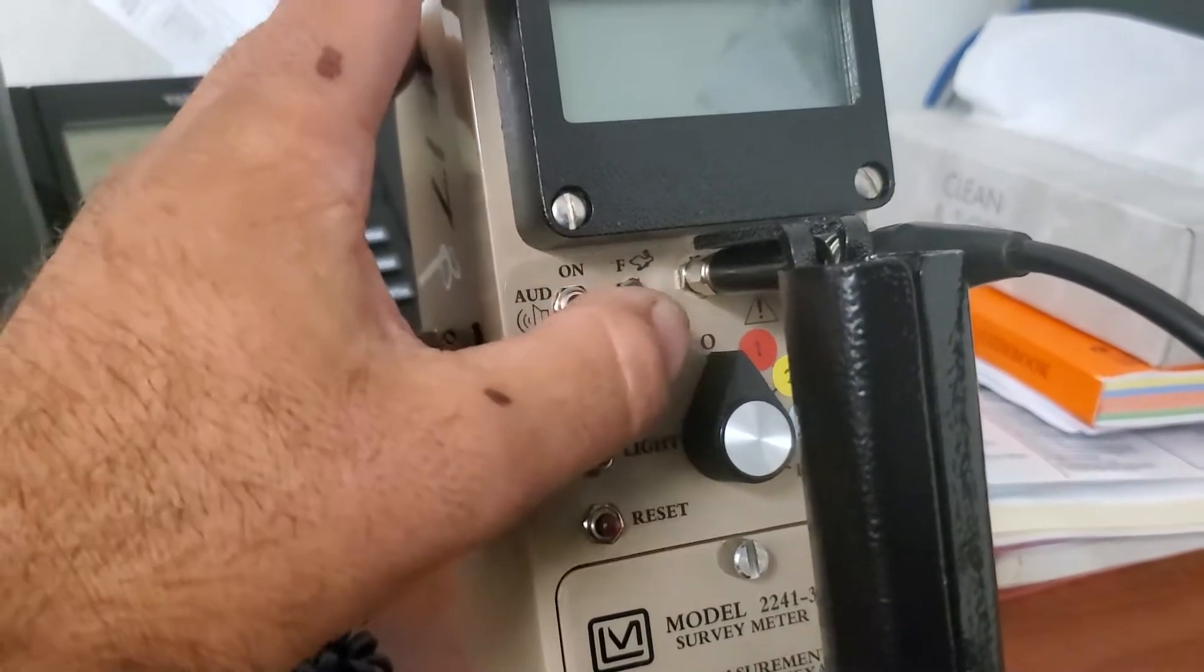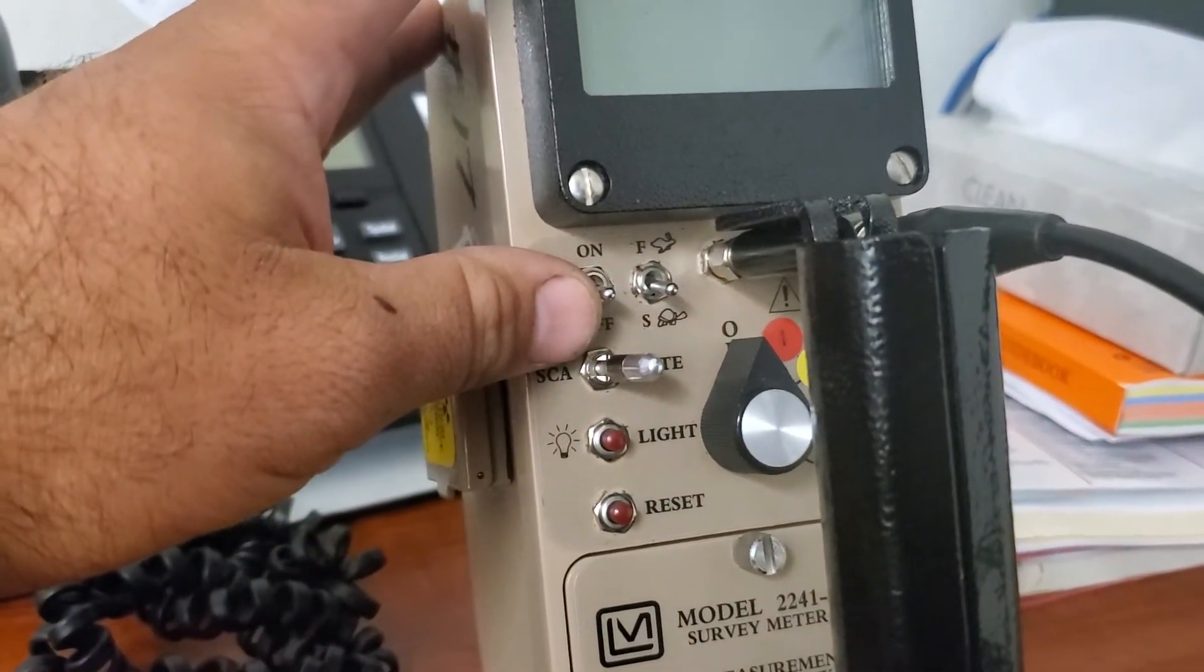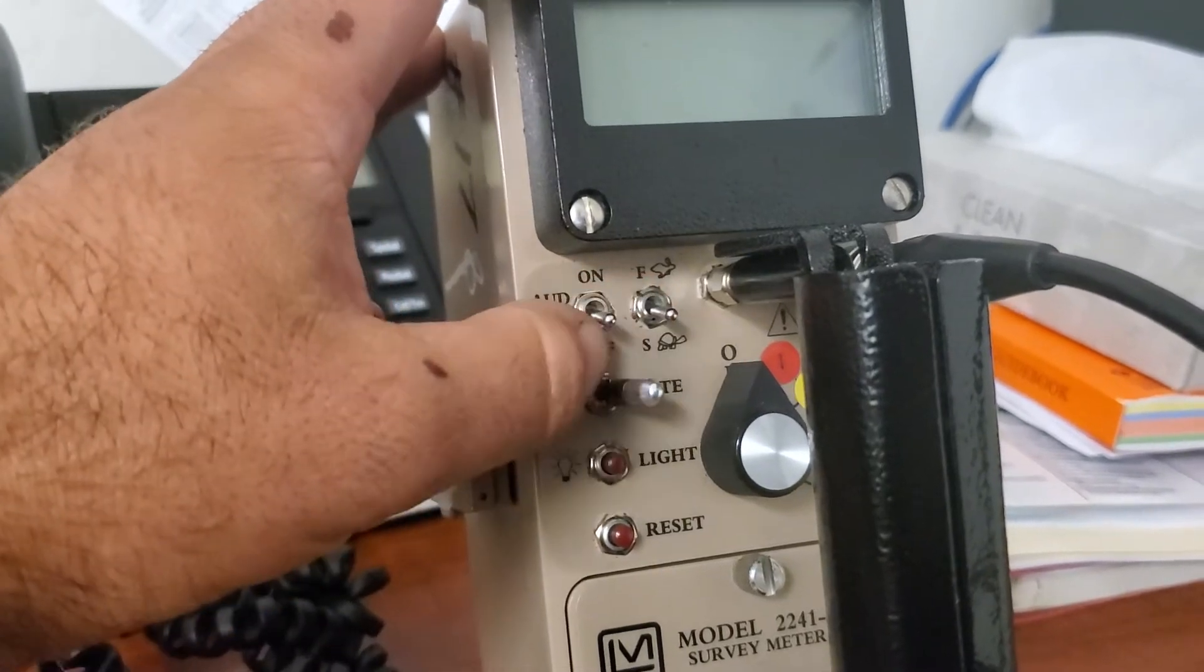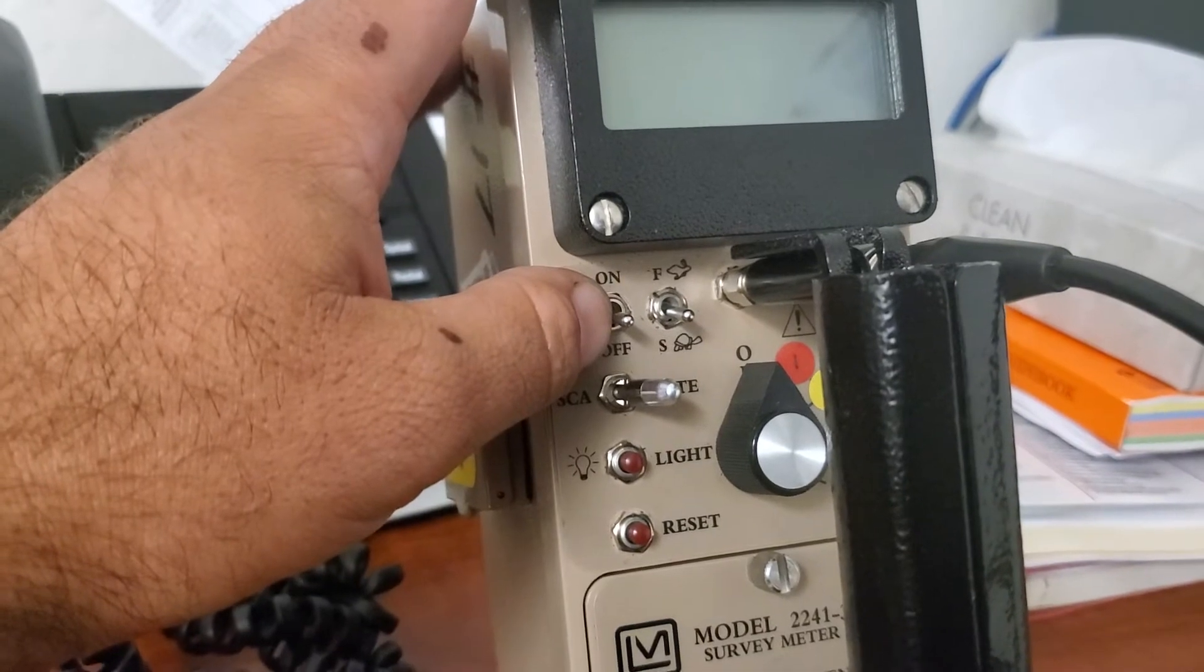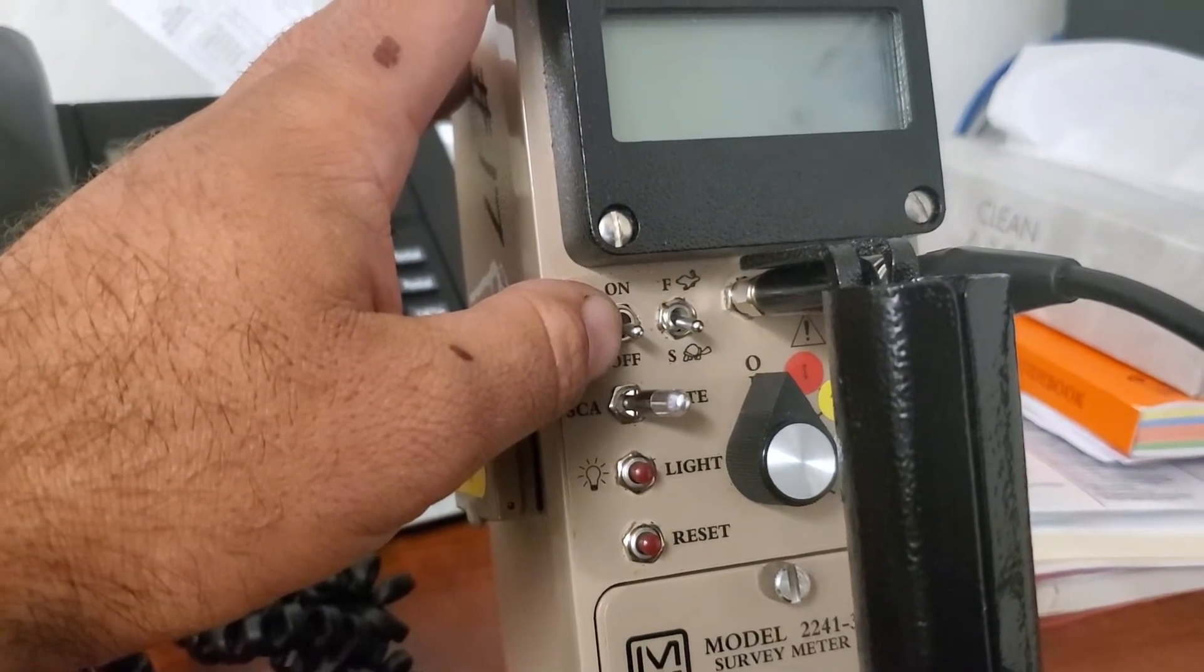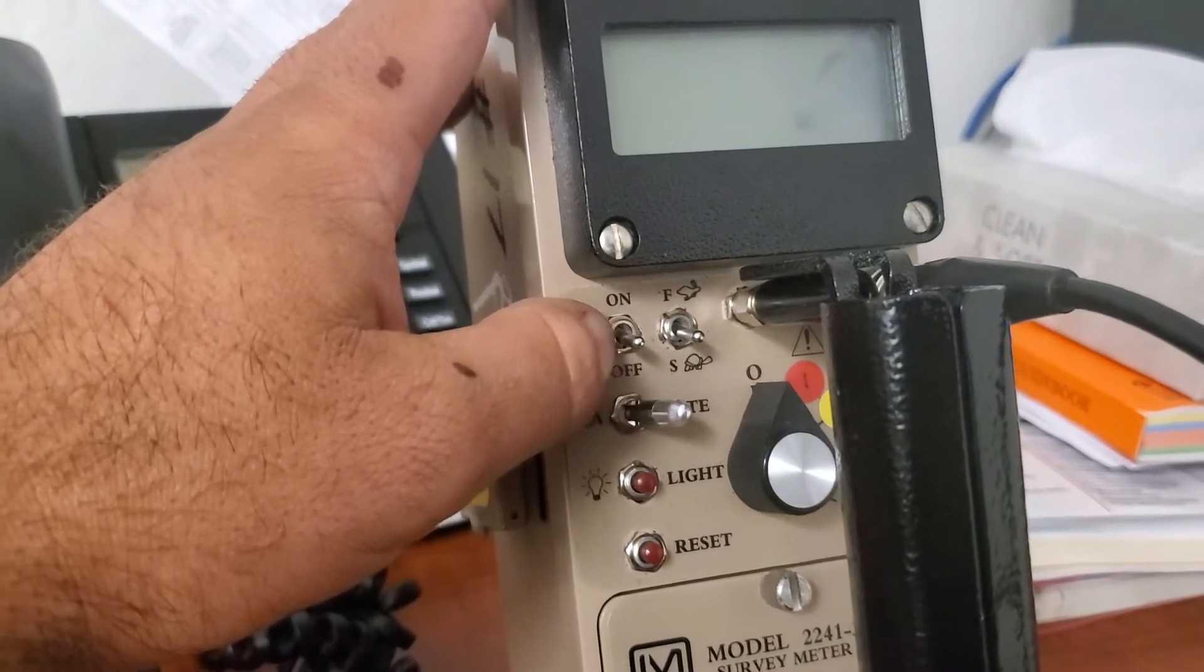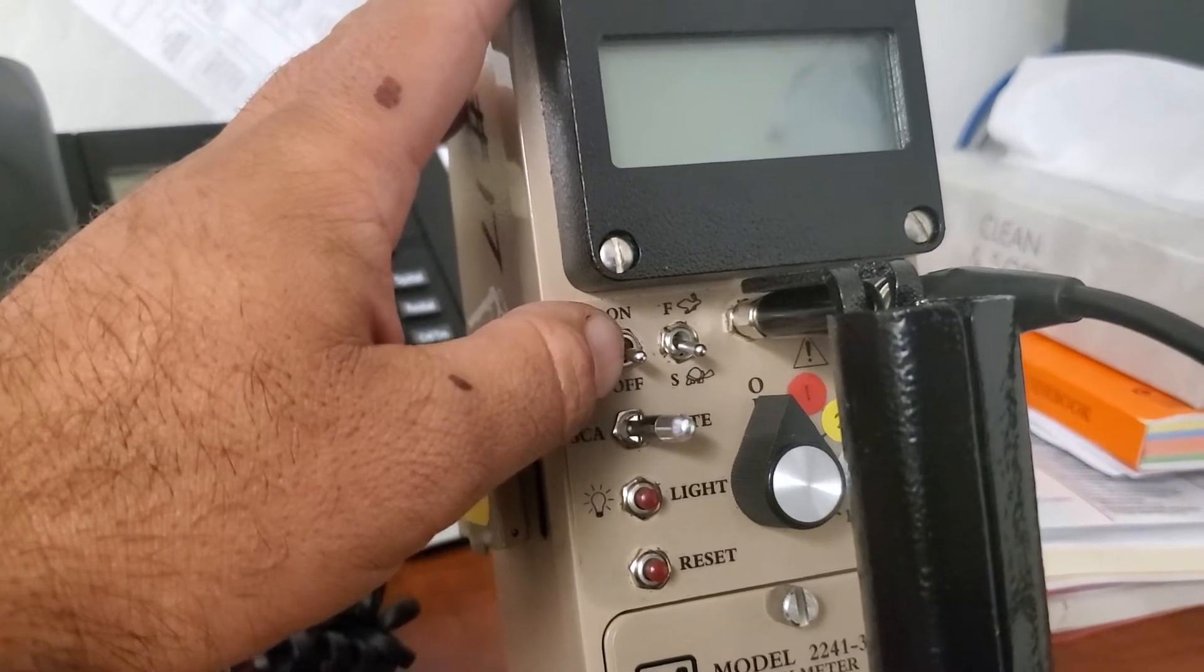Next toggle switch right here is the FS switch. The F has the rabbit, the S has the slow. Fast and slow. This is how fast the probes you are using are reading the environment around them. The fast range has more variance. If you're trying to get more dialed in, a more consistent number, switch it down to S and you'll get less variance on the slow setting.